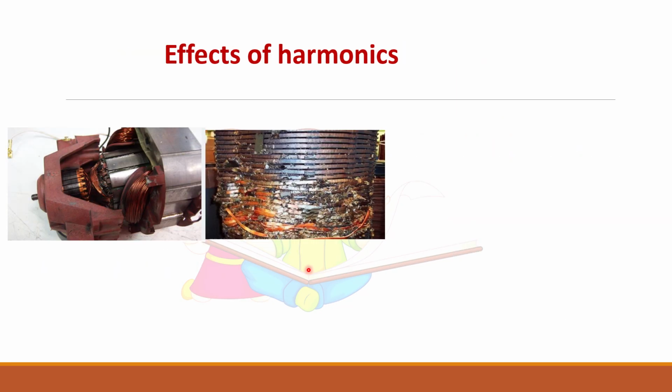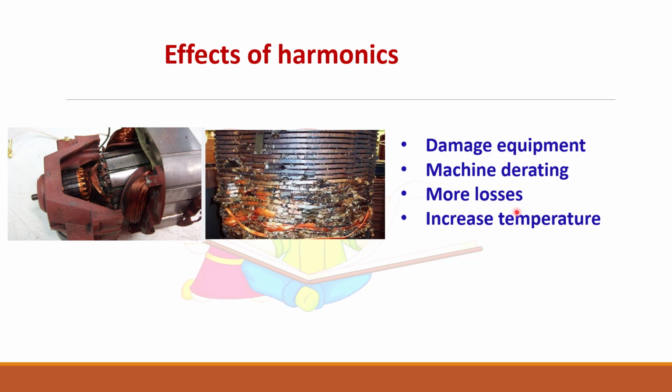If you see the effect of harmonics, it can damage the equipment, it can derate the machine, more losses will be there, and it will increase the temperature. Sometimes even at home you can feel it: when there is a power failure and your home inverter is working with a square wave inverter, you may get a noise from your ceiling fan, or it may vibrate. All these things are because of harmonics.